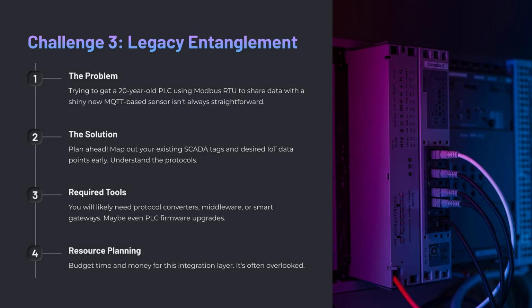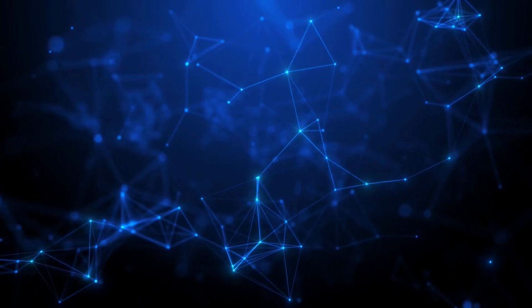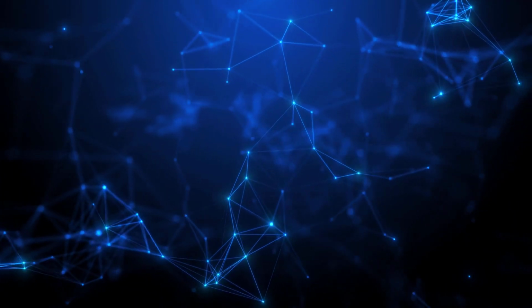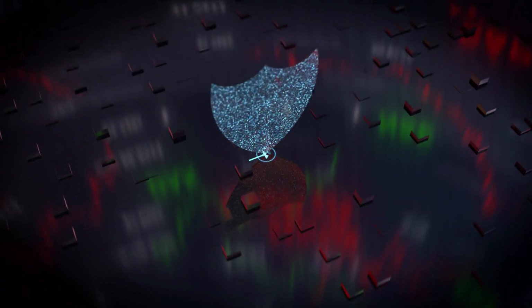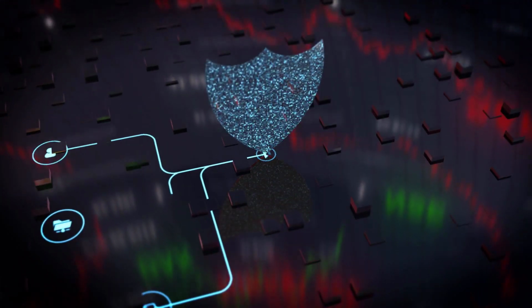Legacy entanglement. Trying to get a 20-year-old PLC using Modbus RTU to easily share data with a shiny new MQTT-based sensor isn't always straightforward. My advice: plan ahead, map out your existing SCADA tags and your desired IIoT data points early. Understand the protocols. You will likely need protocol converters, middleware, or smart gateways, maybe even PLC firmware upgrades. Budget time and money for this integration layer. It's where projects often get bogged down.